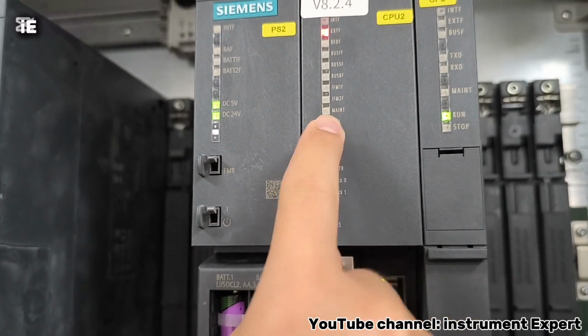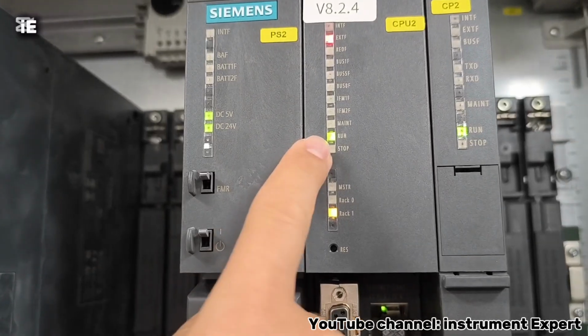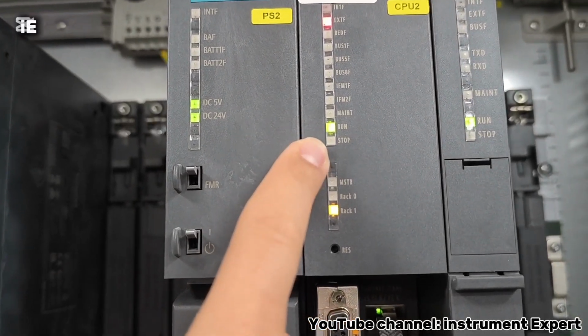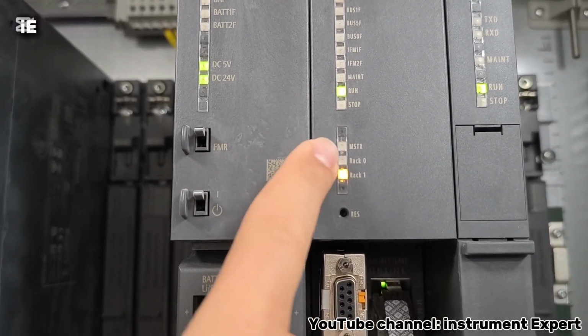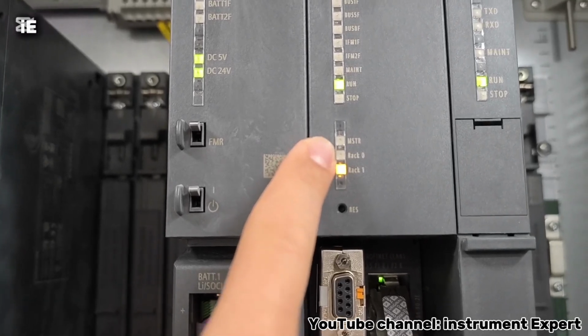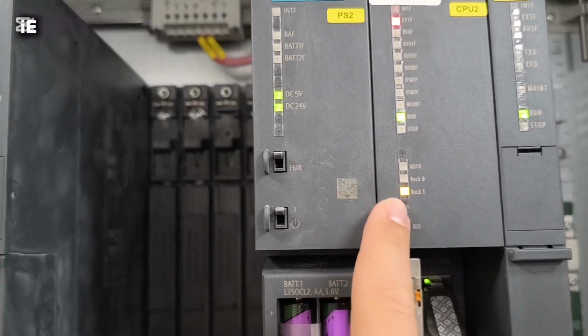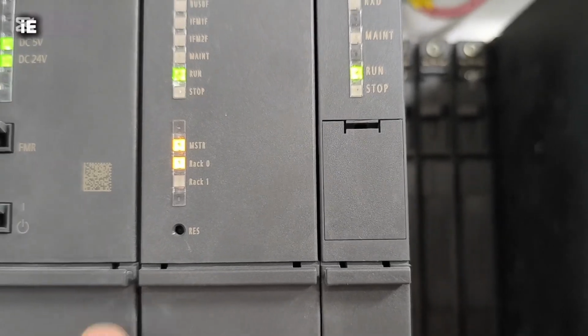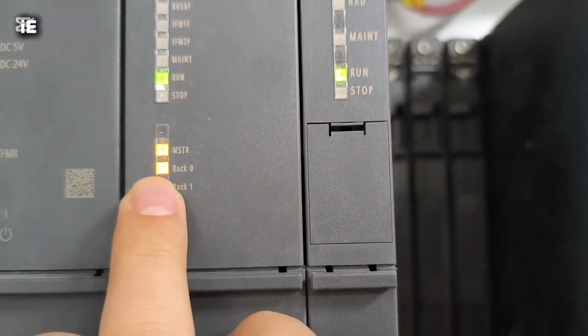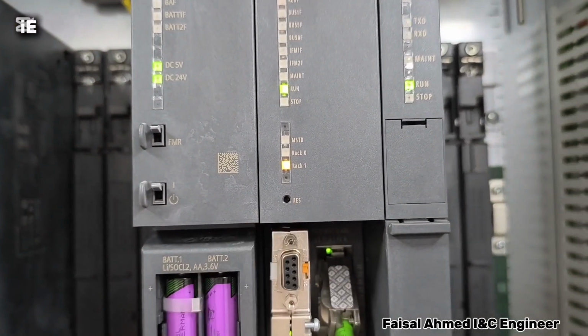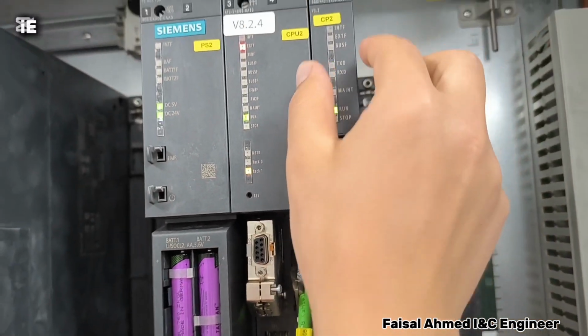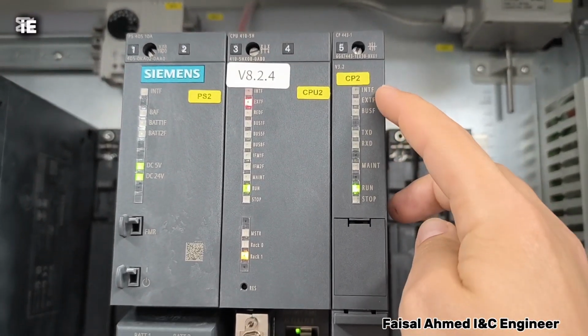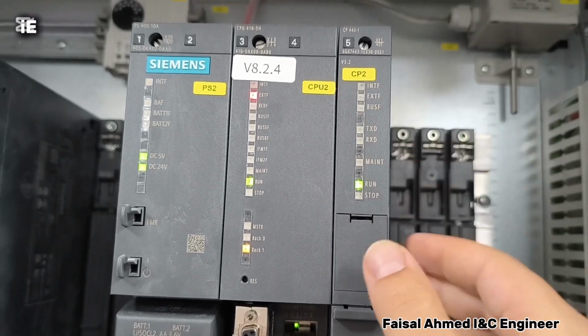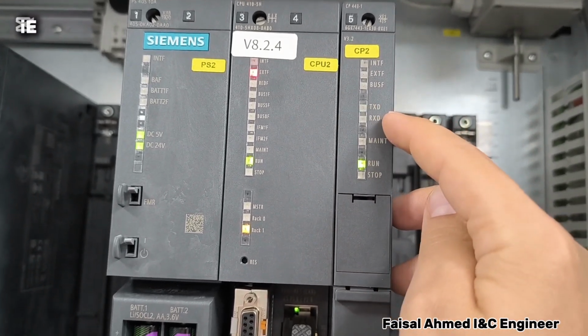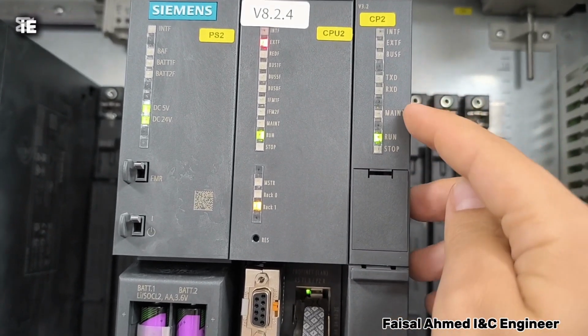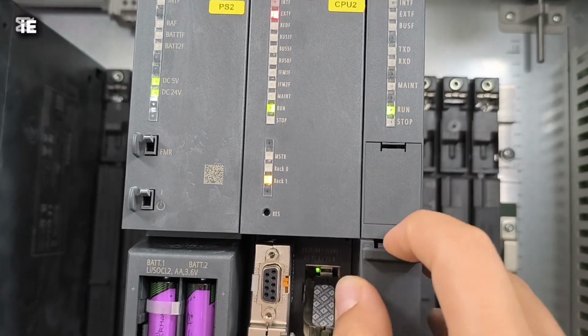Then we have maintenance LED, run status of the PLC, and stop status. Then we have information which PLC is master and in which rack is it configured. So the left one is now master, and the left one is rack 0, and the right one is rack 1. For the communication processor, we have also internal fail, external fail, bus fail, transfer and receive some data, maintenance, run, and stop status.